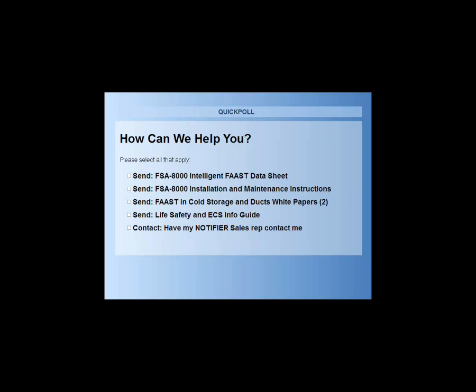Okay. All right. They understand the module situation with FAAST, but they're asking, is it necessary to install a module to reset the FAAST detector when FAAST goes into alarm? Since it sits on the SLC as standard spot detectors, when you press reset on the panel, you would in turn be resetting the FAAST unit as well. Okay. All right. Very good.